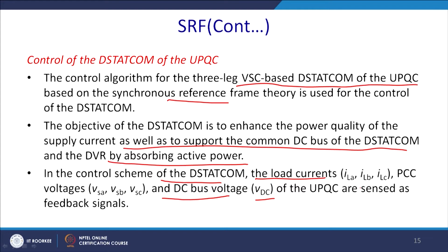So, from there we have the reverse Parks transformation, converting the load current from the ABC frame to the DQ frame. This is a Parks transformation where cos theta and sin theta are obtained from the PLL over the voltages. The PLL signal is obtained from the voltages for generation of the fundamental unit vector for the conversion of the sensed current from ABC to the DQO frame, when you have a zero sequence component of the current.